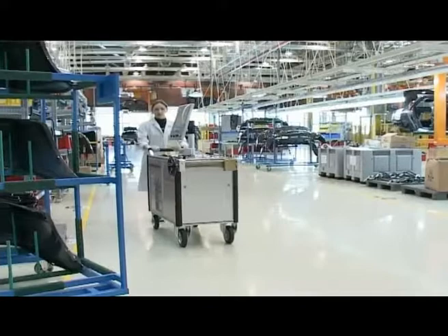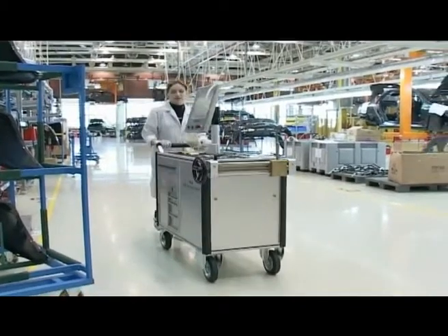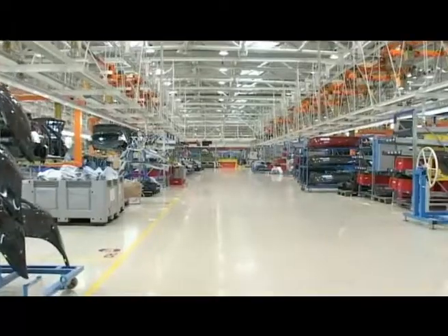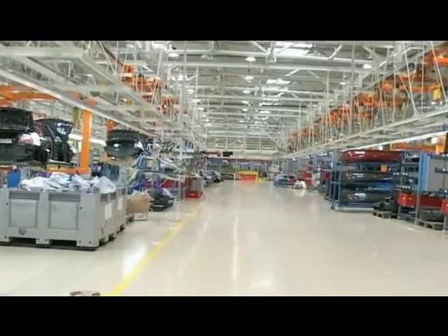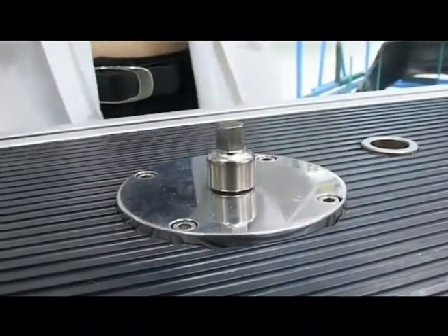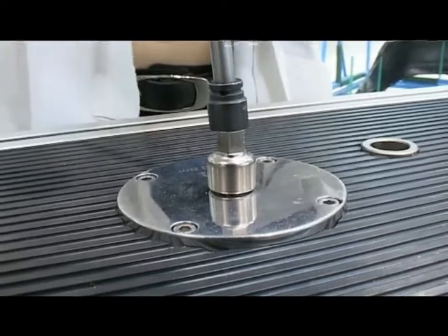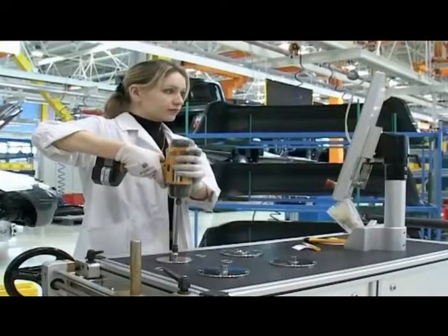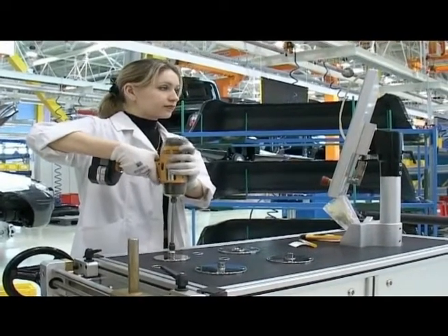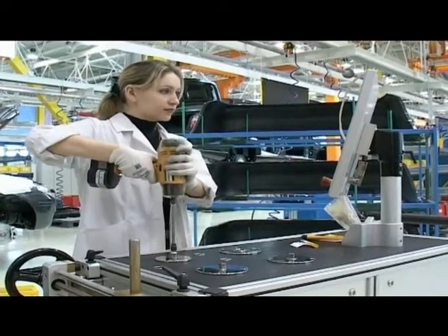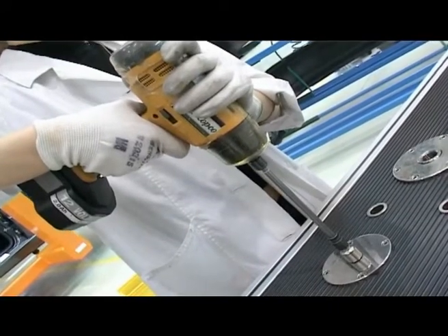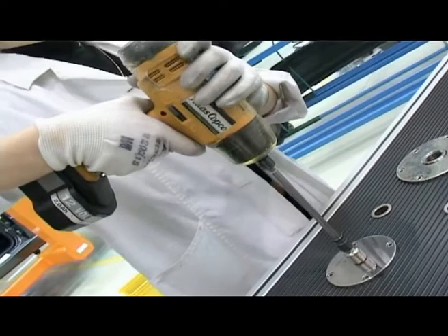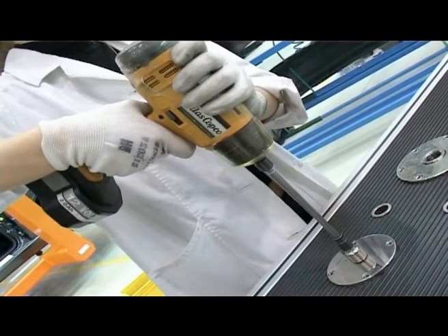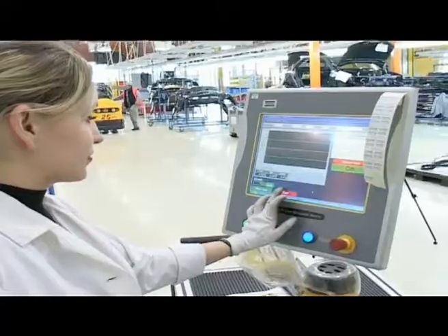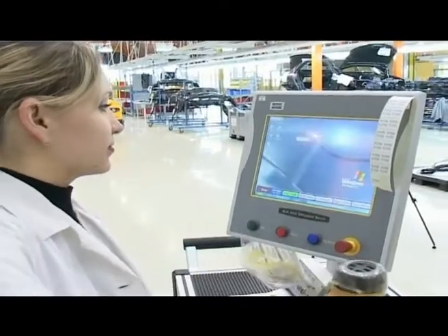When checking tools, the QA operator can move the mobile bench along the assembly line to the different assembly stations. During a check, the operator turns to the bench and carries out 3 tightening operations on the joint simulators. The joint simulators can simulate any joint type within the torque specification of the brake and transducer, for example 35 Nm and 45 degrees.